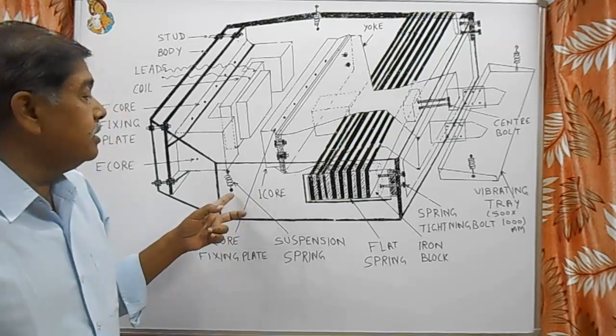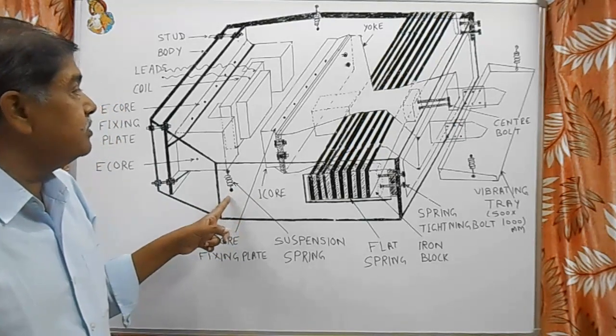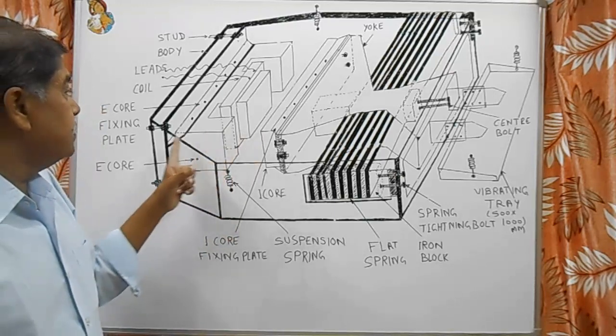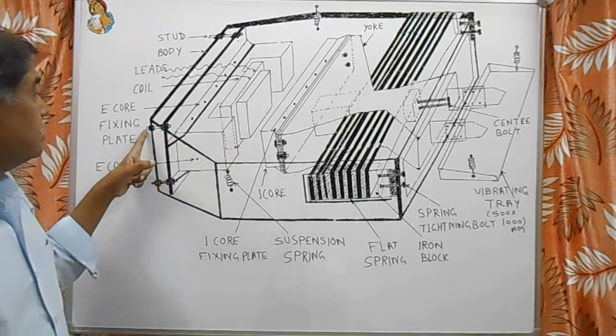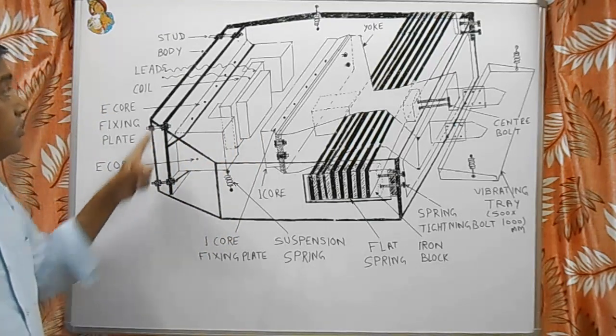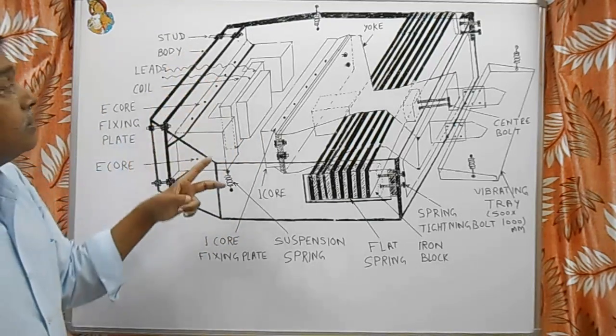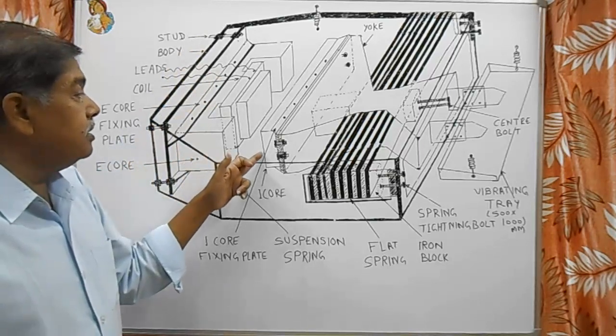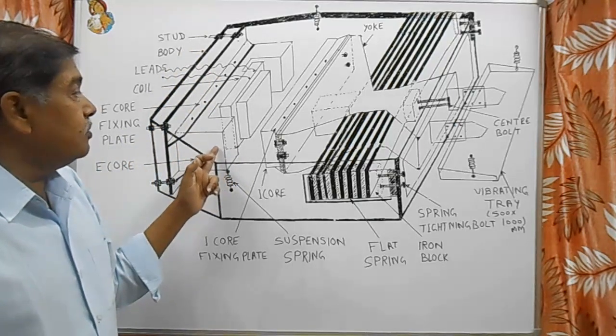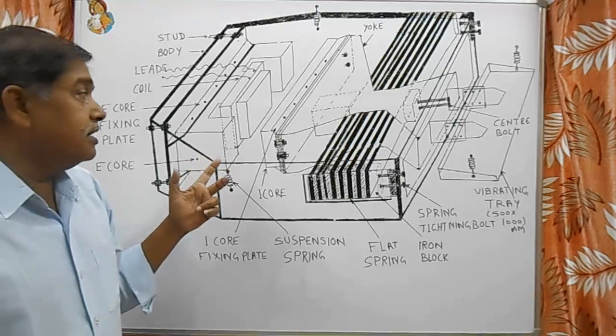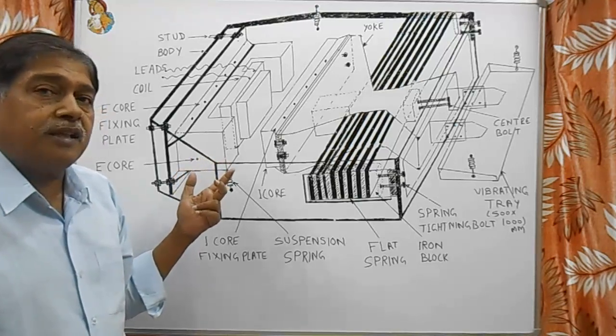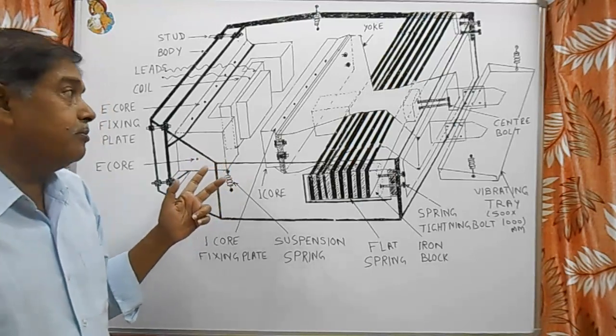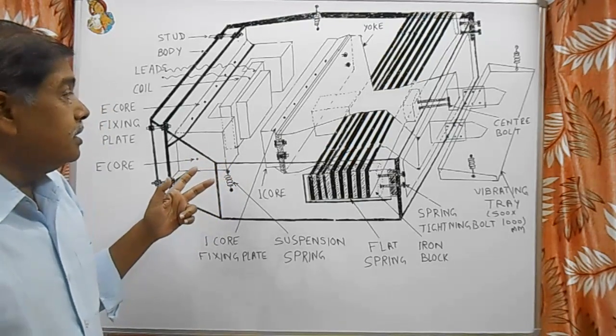The adjustment of feeding is done with the help of adjusting the gap between I-core and E-core with the help of these studs. Here are four studs: one, two, three, and four. These four studs are there to adjust the gap. First we have to check whether the gap between E-core and I-core is correct or not. It should be within 1.5 to 2 mm for proper feeding.